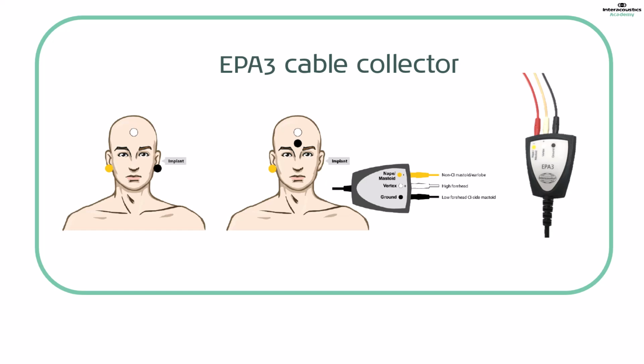There are, however, some steps that can be taken to minimize artifact in evoked potentials recordings in the clinical test setup. The main method for minimizing the likelihood of artifact in the waveform is to reduce the chance for electrical interference from the device to be detected by the recording electrodes. The most successful way to achieve this is to simply increase the distance between the implant and the recording electrodes. This can be done by opting for a 3-electrode montage, with the reference electrode on the contralateral mastoid to the implant. For those of you familiar with EABR testing, this is the same setup.